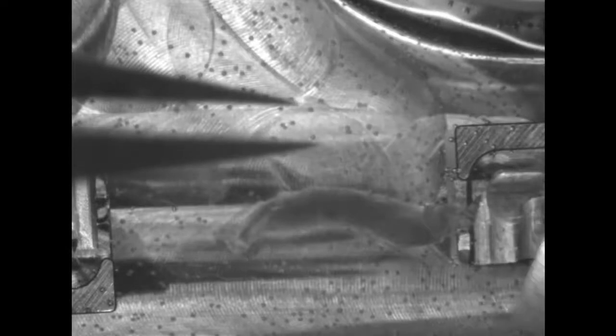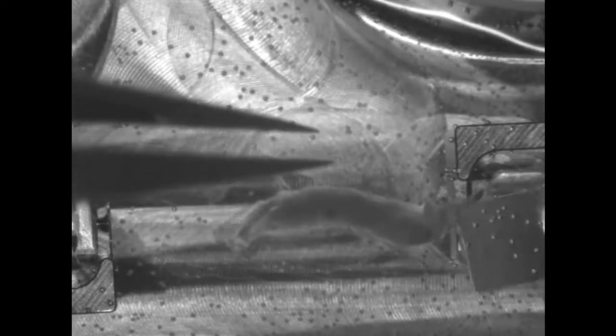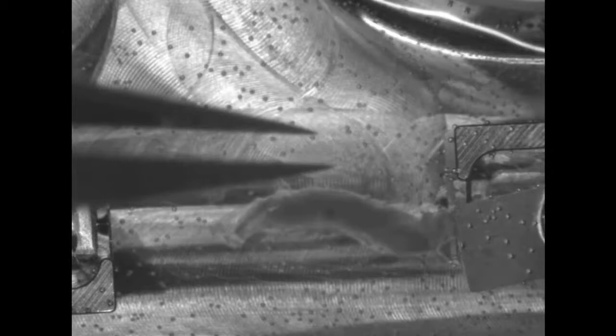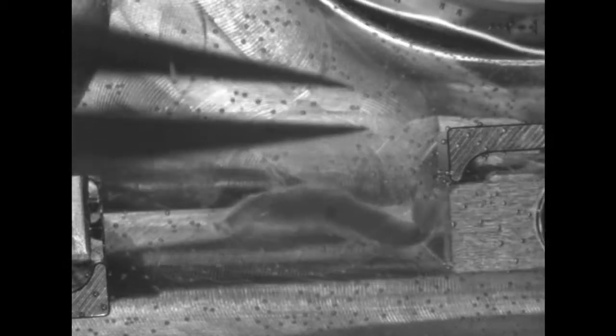When mounting your muscle, lay one end of the tendon over the clamp's edge. When you are ready to clamp the tendon, push down on the back edge of the plate, which will bring the front edge up. You may need to loosen the screw so you have flexibility to adjust the height of the plate. You can then swing the plate over above the tendon and clamp straight down on the tendon itself.